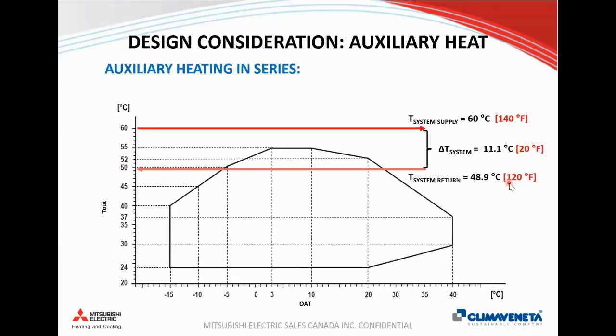Yeah, I get this question a lot. I anticipated this. So really the key for a heat pump to deliver heat to the building isn't really the outside air temperature. Well, it is, but it's also the return temperature from the system. So if this is our operating limit, and if we pretend we have a typical condensing boiler design of 140F, 120F with a 20F delta, this is the design delta T that we're going to see on our design day. So Toronto, it'll be minus 23. We have less heat losses as it gets warmer. So our return temperature is basically always going to be above this line.